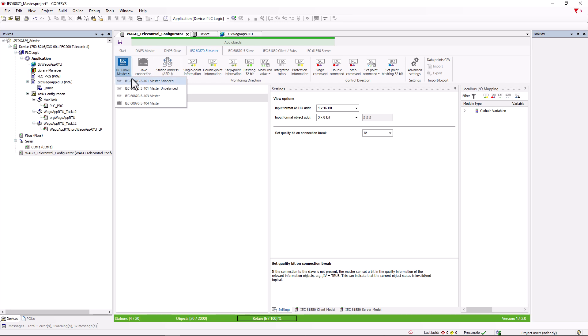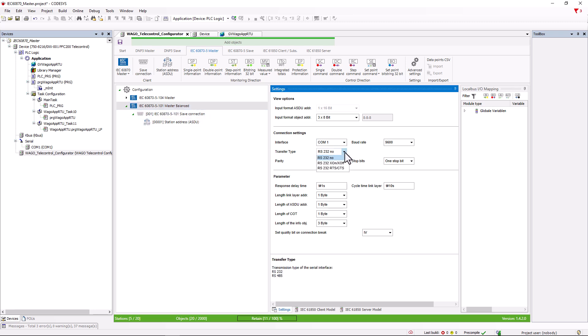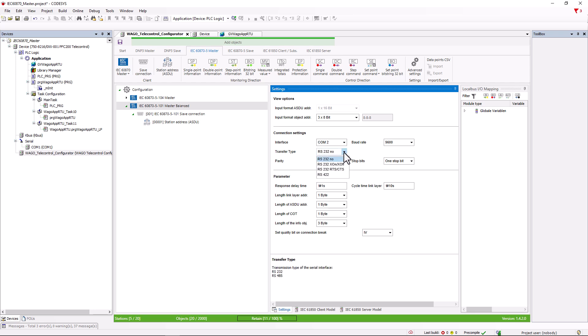Serial Master 101. Let us now take a look at the Master 101, starting with balanced communication. With balanced communication, both participants, Master and Slave, are able to send, so a spontaneous message can be sent directly by the Slave and is not requested by the Master through cyclic polling. This also explains why we can only select RS-232 here and RS-422 from COM-2 onwards, as only these two transmission types support simultaneous sending and receiving.